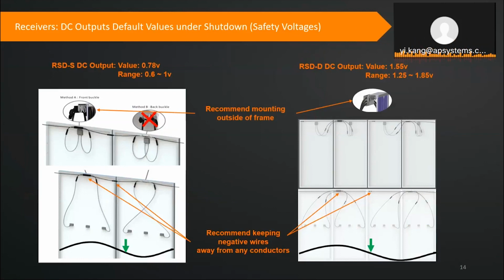Next, some details about our receiver. We recommend installing it outside of the frame because we have clips. Originally, you can clip outside or inside. But after 3 years, we learned from the field to see if there is any concern about failure. With the inside, there is a higher possibility that you will damage the backsheet, right? So right now we only recommend that customers install our device outside of the frame, using the frame as the barrier. And when the worst case happens, if they fail, they still have a barrier to protect your panel backsheet, and you will never damage your panel.